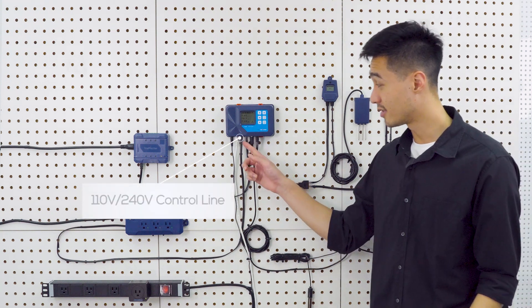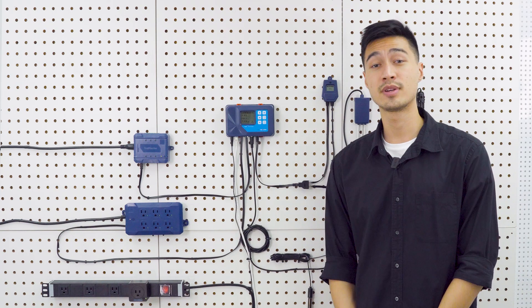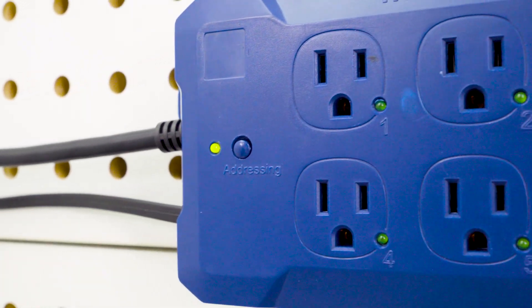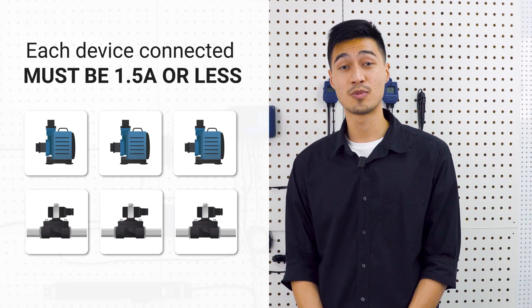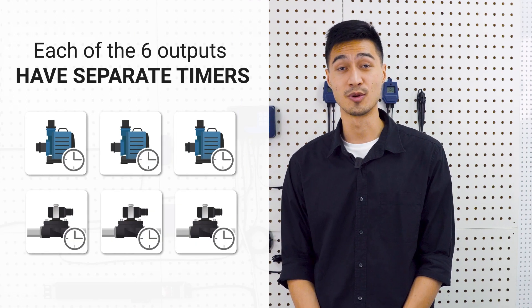There's a 110 volt and 240 volt control port at the bottom of the controller to connect the irrigation device modules and control devices like pumps and solenoids. The 086110 control board is designed to control small 110 volt pumps or solenoid valves and it has six separate 120 volt outlets. Each device connected must be 1.5 amps or less, and each of the six outputs will have separate timers to control them.